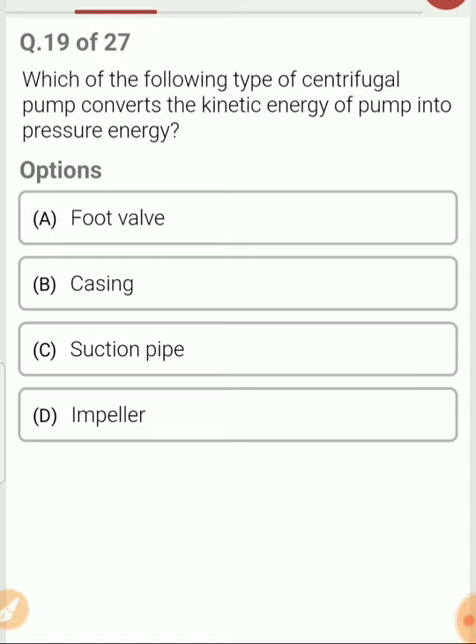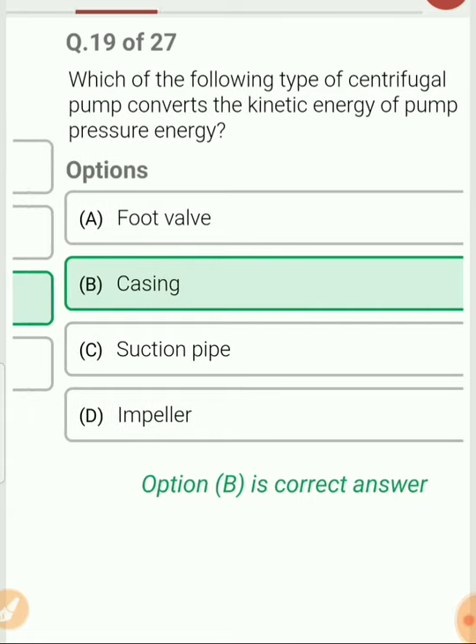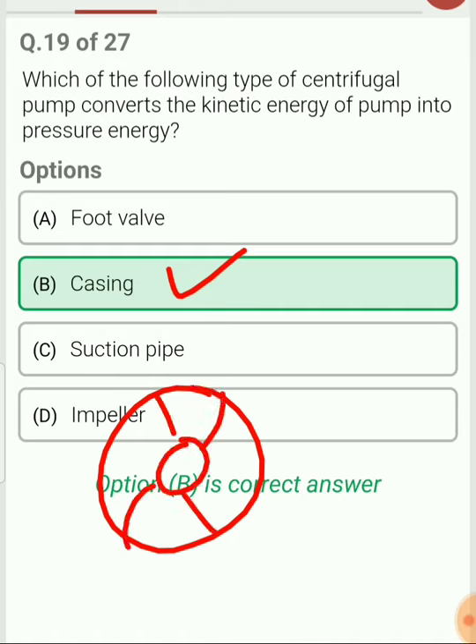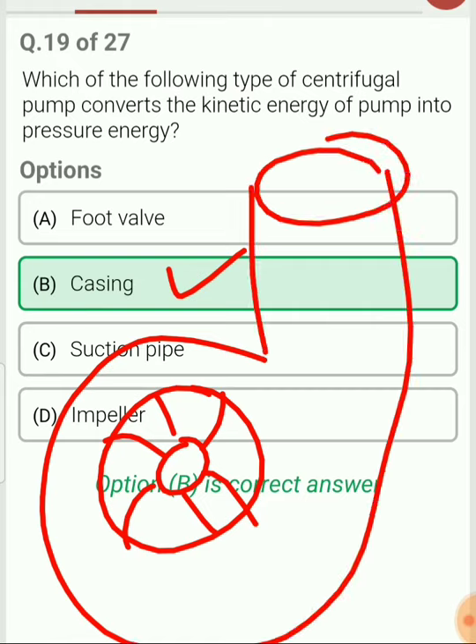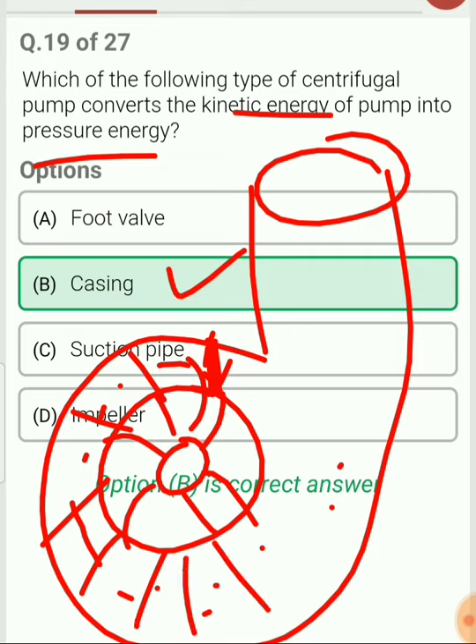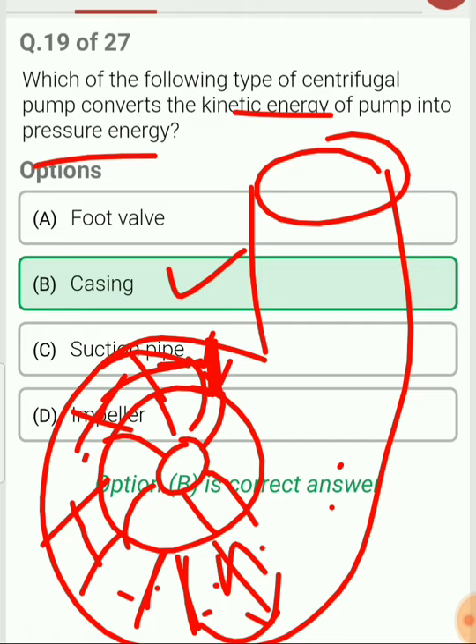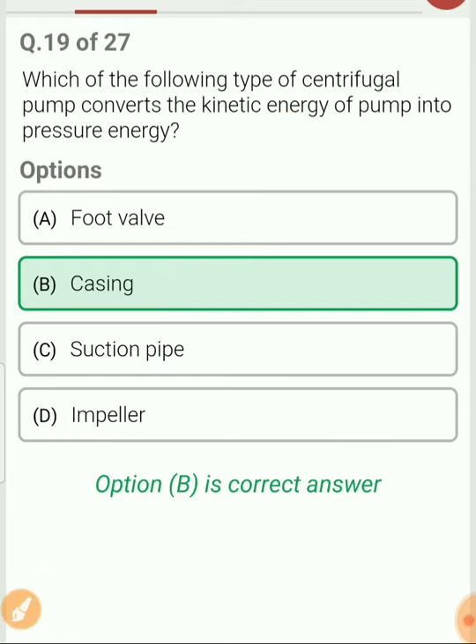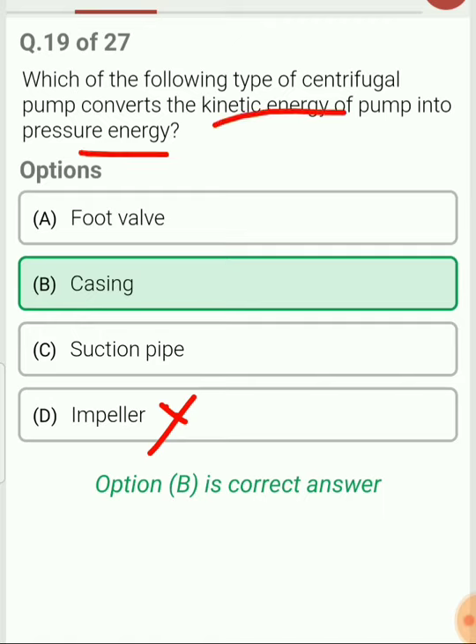Question 19. Which component of the centrifugal pump converts kinetic energy into pressure energy? The answer is casing. In the impeller, both kinetic energy and pressure energy are increasing, so impeller is not the answer. In the casing, as water enters from the impeller, the gap gradually increases and kinetic energy converts into pressure energy. So the component that converts kinetic energy into pressure energy is the casing.